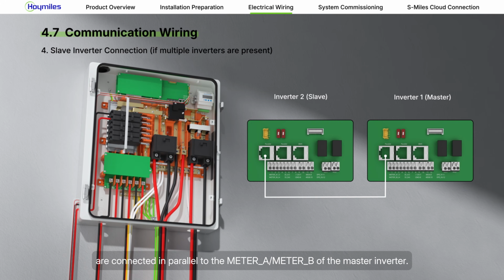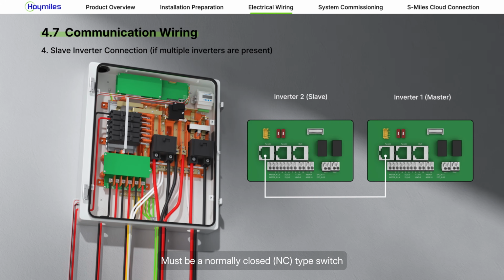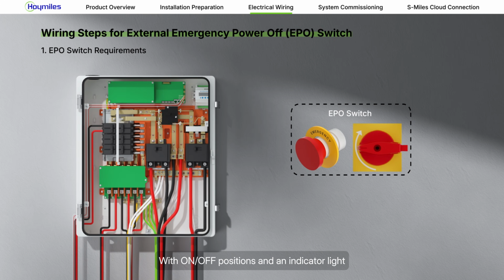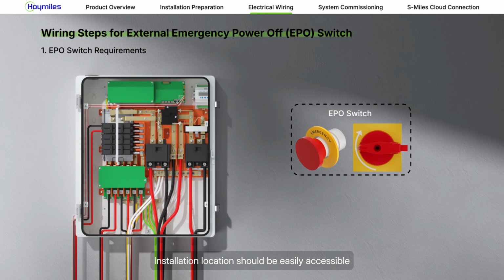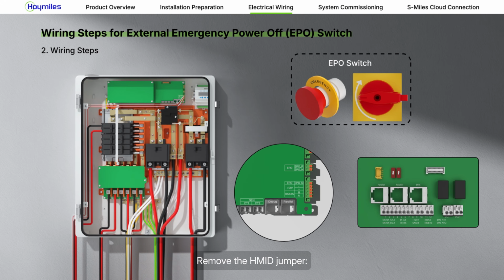the master inverter. Must be a normally closed type switch, with on or off positions and an indicator light. Protection rating not lower than NEMA 3R. Installation location should be easily accessible. Remove the HMID jumper. Locate the EPO-P and EPO-N terminals on the HMID and remove the jumper between them.